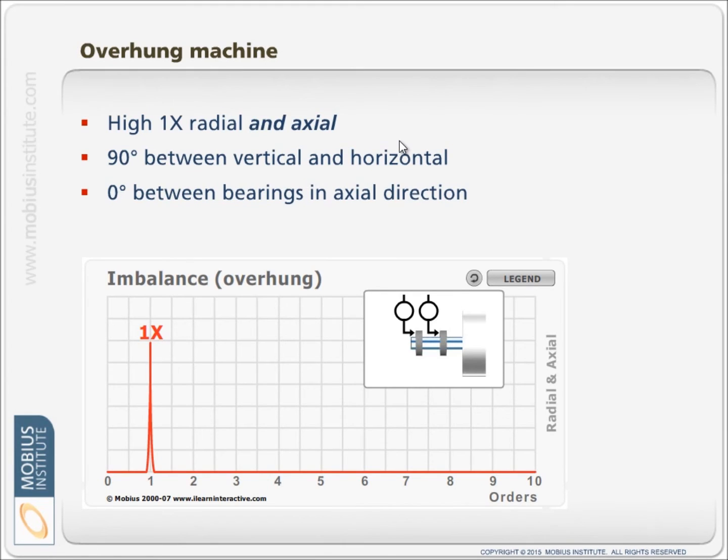And we can look for the 90-degree phase difference between vertical and horizontal, and we can look at the zero-degree phase difference when measuring the two bearings in the axial direction.